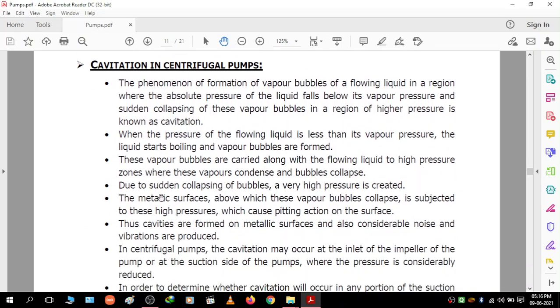Next is cavitation in centrifugal pumps. Cavitation is the formation of vapor bubbles of a flowing liquid in a region where the absolute pressure of the liquid falls below its vapor pressure. When the pressure of the flowing liquid is less than its vapor pressure, the liquid starts boiling and vapor bubbles are formed.